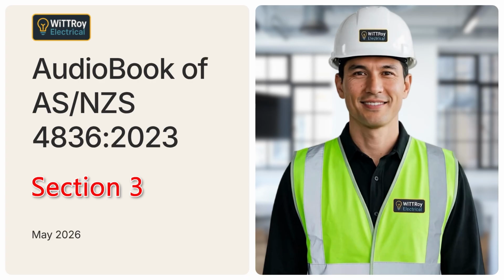The correct equipment must be identified. The correct isolation points must be found. All sources of supply must be considered. The isolation must be secured. Stored energy must be discharged where needed. Then the equipment must be tested to prove it is de-energized. This is the practical process that protects people before work starts.